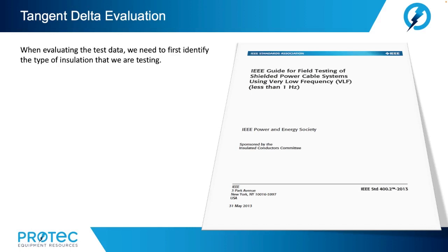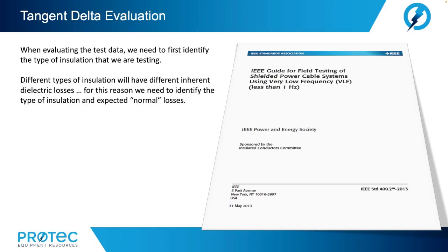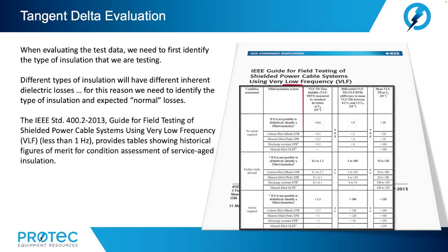Now, when evaluating your test data, we need to first identify the type of insulation that we are testing. Different types of insulation will have different inherent dielectric losses, as we discussed earlier. For this reason, we need to identify the type of insulation and expected normal losses. The IEEE 400.2-2013 Guide for Field Testing of Shielded Power Cable Systems Using VLF provides tables showing historical figures of merit for condition assessment of service-aged insulation.